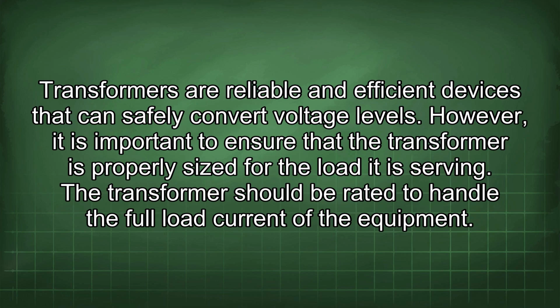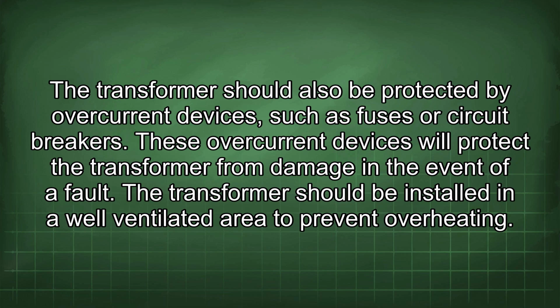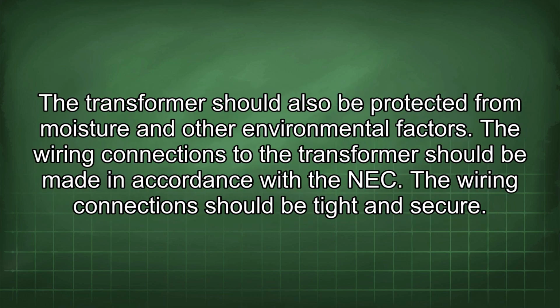Transformers are reliable and efficient devices that can safely convert voltage levels. However, it is important to ensure that the transformer is properly sized for the load it is serving. The transformer should be rated to handle the full load current of the equipment. The transformer should also be protected by overcurrent devices such as fuses or circuit breakers. These overcurrent devices will protect the transformer from damage in the event of a fault. The transformer should be installed in a well-ventilated area to prevent overheating. The transformer should also be protected from moisture and other environmental factors.